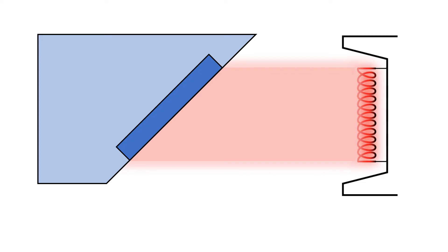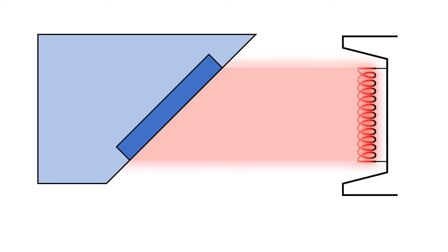There are three things that influence the size of the incident electron beam. One is the width of the filament coil. Two is construction of the focusing cup. And three is position of the filament inside of the focusing cup.